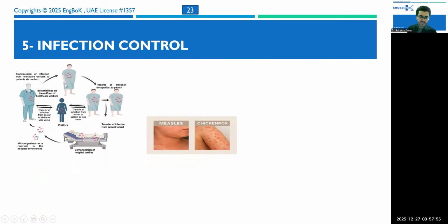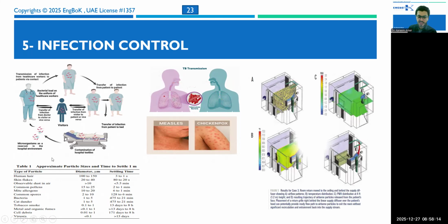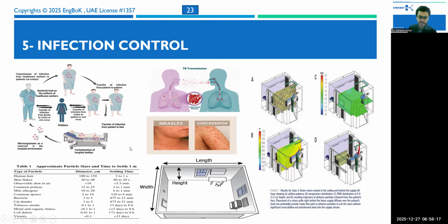How the infection spreads from person to person and from the reservoir or source to the host, a chain of infections, different types of pathogens and infections, airborne, waterborne, or bloodborne, or surface, direct and indirect, size of particles, and selection of recommended filters, MERV rating as per ASHRAE 170, how to calculate CFM based on air change per hour requirements and the pressure regime in the room, CFD analysis for different locations of supply and return diffusers and grilles.